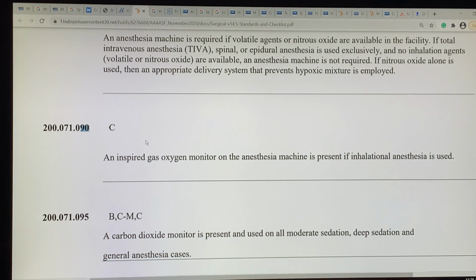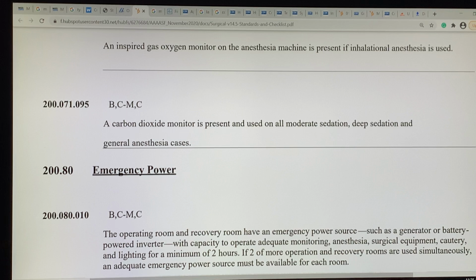0.90, an inspired gas oxygen monitor on the anesthesia machine is present if inhalational anesthesia is used. I'll be vague on this, but most people are just going to use the oxygen until they work with anesthesia, and you want room to grow and change. Your anesthesia machine will have this monitor, and a carbon dioxide monitor will also be on the machine.